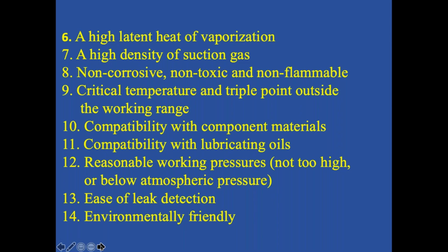Then compatibility with other component materials, that is with the condenser, evaporator, controls, and piping, the material should be compatible. Also, the compressor requires lubricating oil, and the refrigerant should be compatible with the lubricating oil. There are mineral oils, synthetic oils, and so many varieties of oil, POE oils, PAG oils, and every refrigerant has some compatibility with the lubricating oil. Then reasonable working pressures. We don't want too high a working pressure, and we should not go below atmospheric pressure. For example, ammonia has a boiling point of minus 33 degrees centigrade. Up to that point, you can use it at positive pressure. The discharge pressures also should be reasonable, 15 bar, 16 bar, 17 bar, not beyond that.